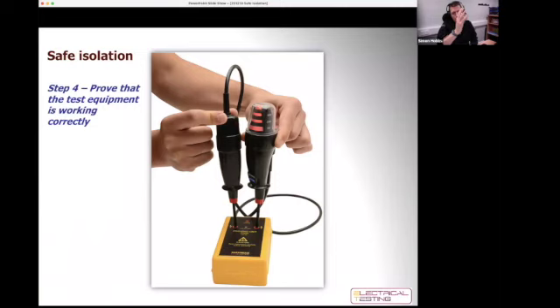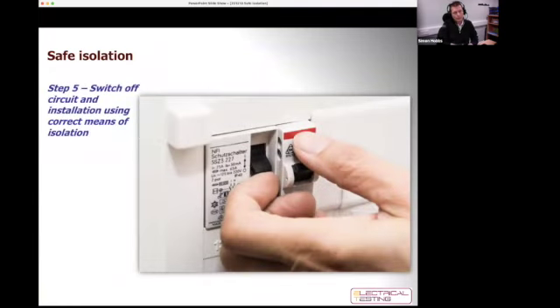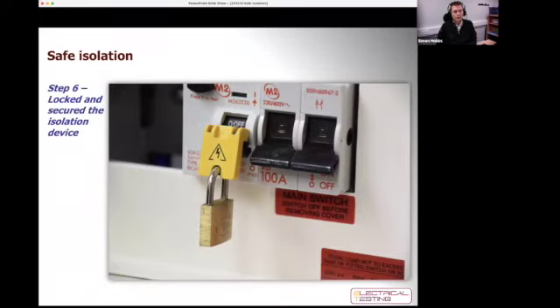Okay, so I've asked permission, I've identified what I'm going to isolate, I've selected my equipment and made sure that it's working. I'm now going to switch the circuit off. So I use an appropriate means of isolation device that complies with regulation 12 of the Electricity at Work regs. And I switch it off, and then in accordance with regulation 13, I lock it off and secure that device so it can't come back on.